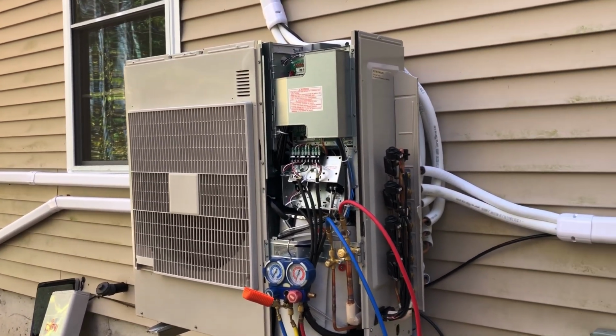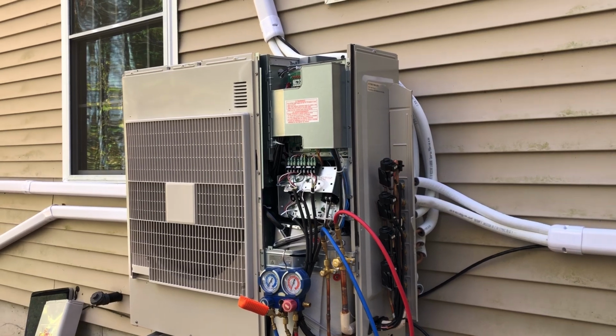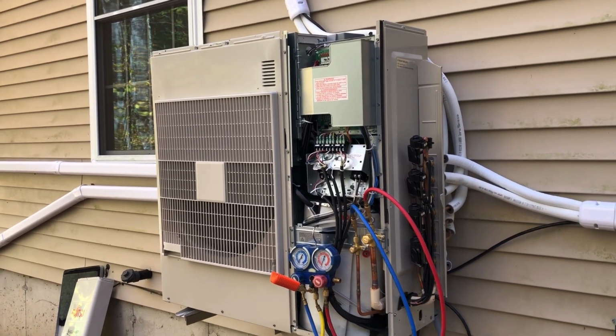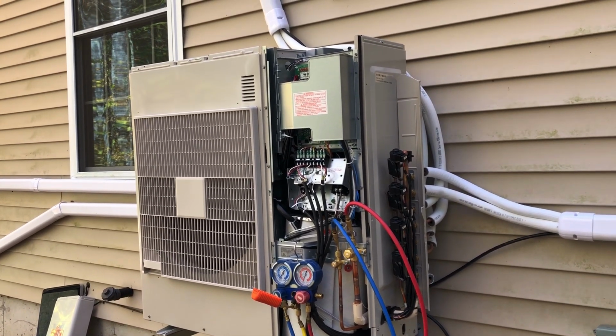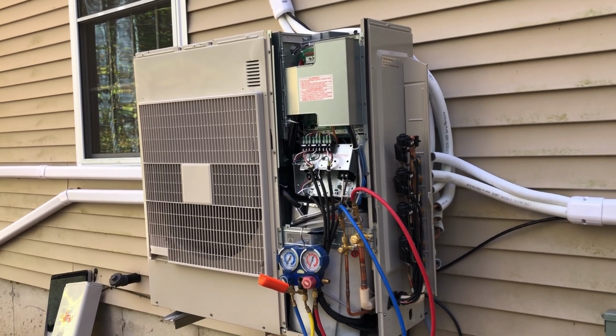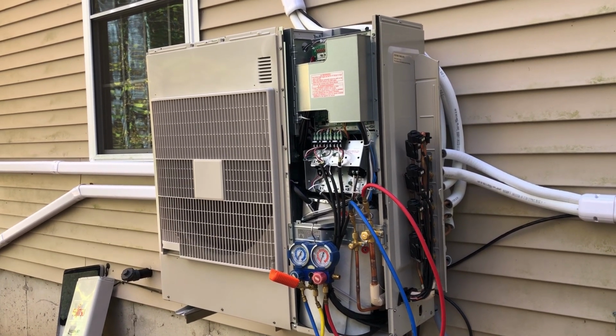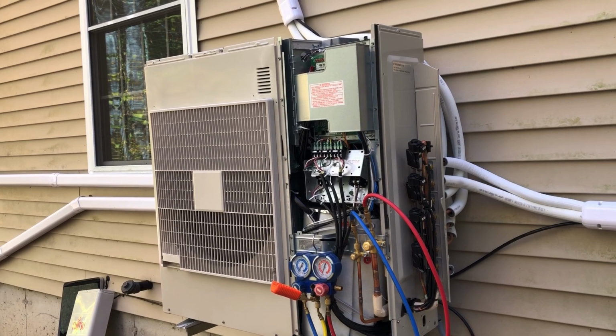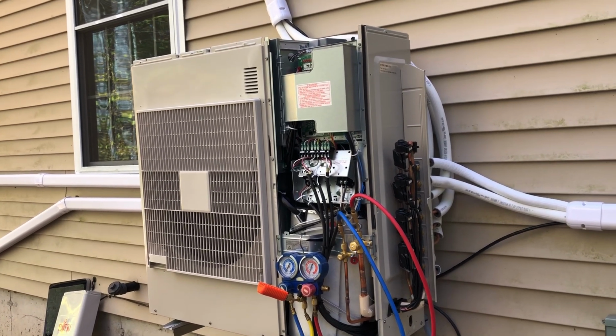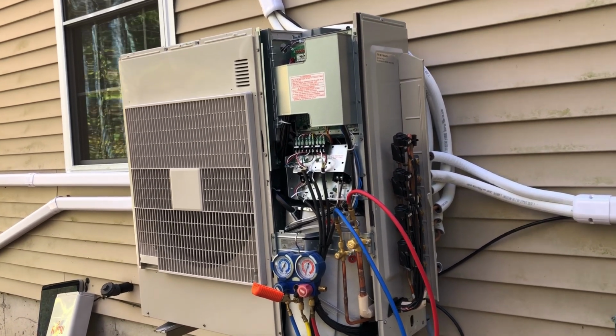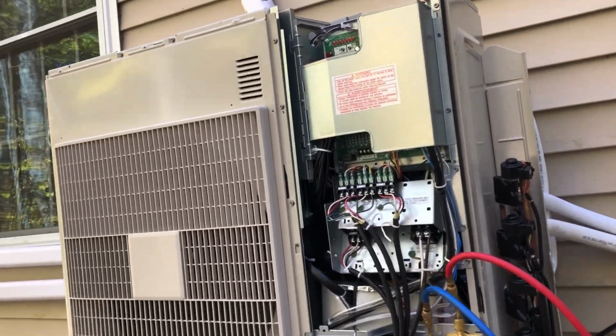In this case, this was set up specifically for 4 zones, so I was allowed to go up to 164 feet before I had to add any refrigerant. But that being said, you must check your installation manual, because it'll tell you if you need additional refrigerant, and if so, how much to add per foot, and you'd have to scale it.